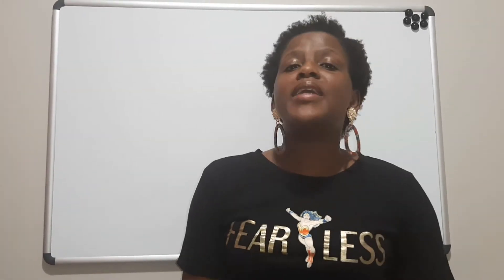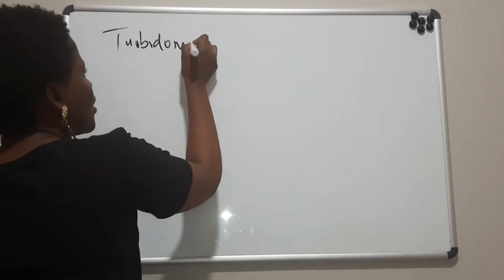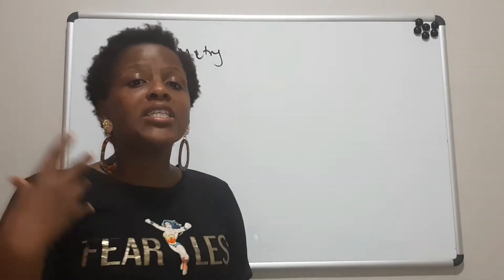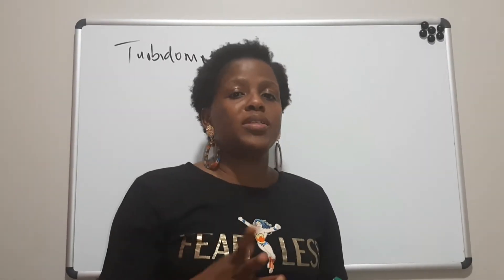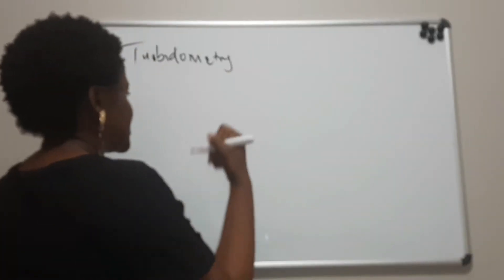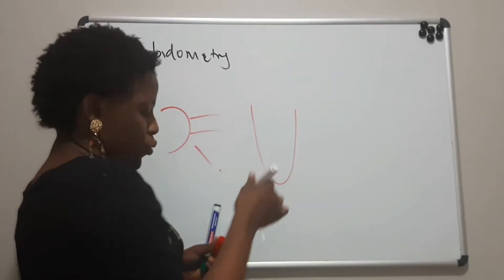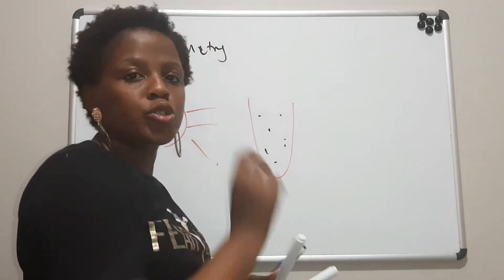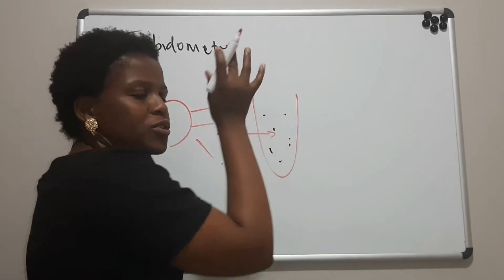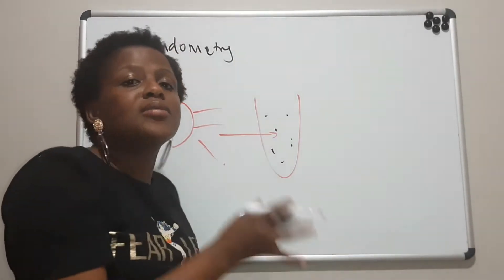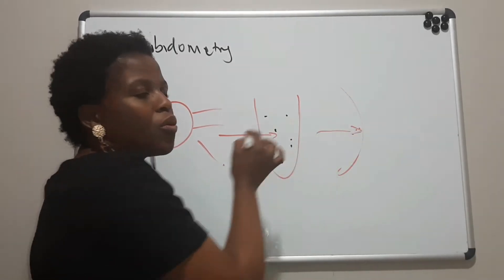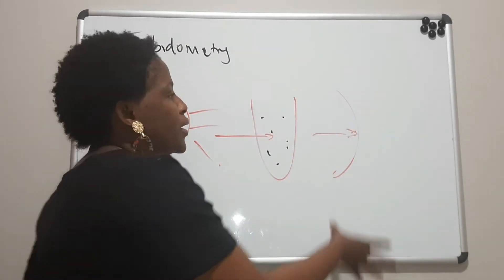In this video, I want us to talk about turbidometry and nephelometry. We will start with turbidometry. If you remember from the video we did when we were talking about spectrophotometry, turbidometry also uses the normal spectrophotometer. A beam of light is shone through a cuvette that contains particles suspended in a solution. Those particles will either absorb the light or transmit it. The transmitted light then goes into the detector, which detects the amount of light transmitted.